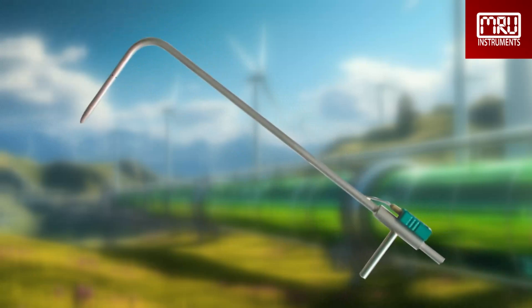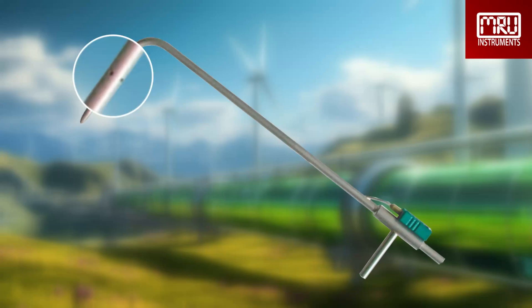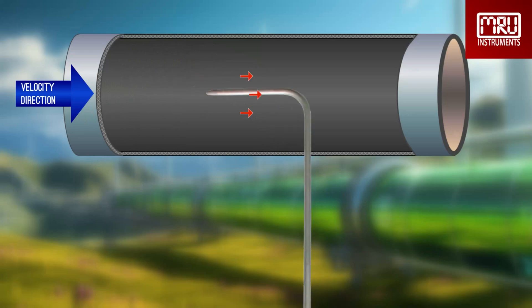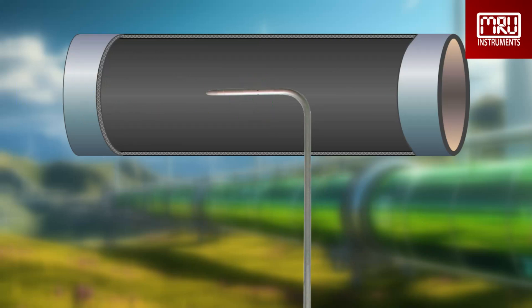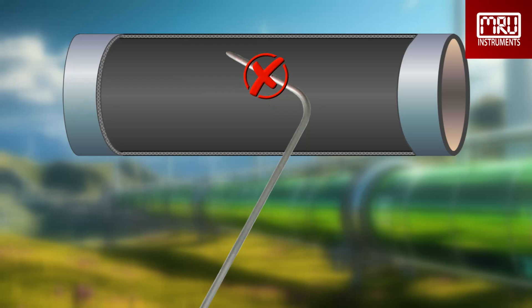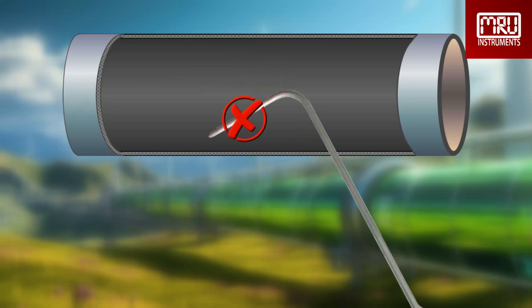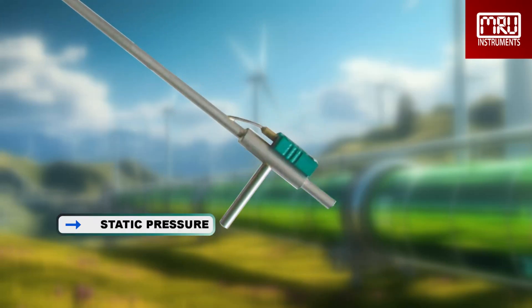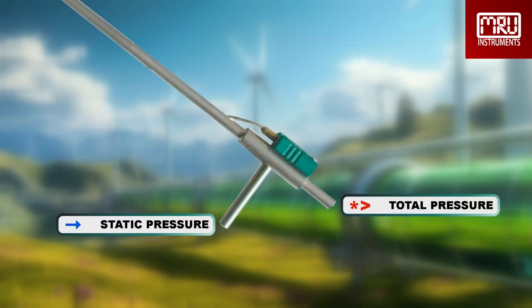Seen here is the L-type pitot tube with temperature measurement. Here magnified are the static pressure entrance ports. The entrance port for total pressure is at the tip of the pitot tube. When measuring flow velocity, it is important that the total pressure port entrance points against the flow direction, and that the pitot tube is straight inside the duct. The measurement will be incorrect when the pitot tube points either too high or too low. At the other side of the pitot tube we have the hose connection for static pressure, the hose connection for total pressure, and the connection for temperature measurement.